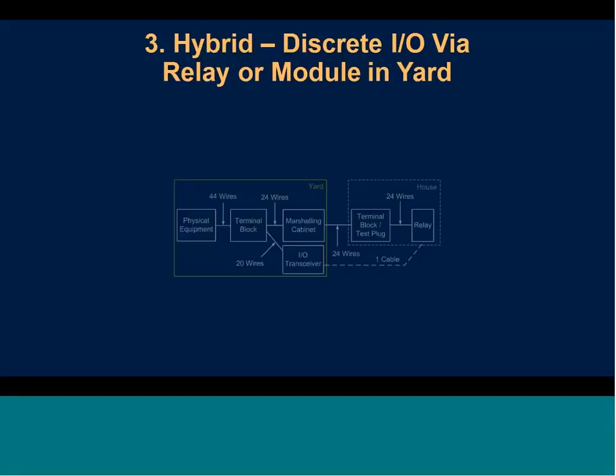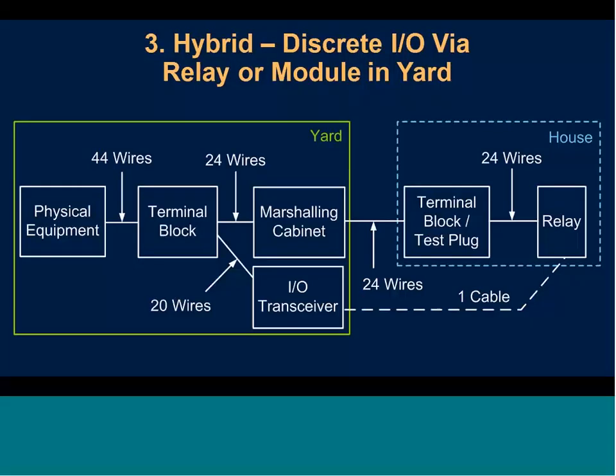Another way that we can reduce the amount of wiring is using a hybrid system where we still hardwire our analog signals, but we can use an I/O module out in the yard so that we can consolidate all of our I/O signals into a single fiber optic connection. Using that same example, we can segregate our I/O and our analogs. The analogs still get hardwired back into the control house, much like in a traditional setup, but we have the relay communicating with an I/O transceiver out in the yard through a fiber optic cable.